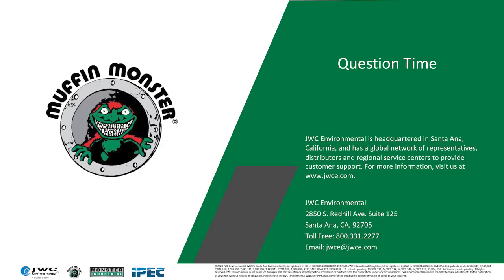Sure. Today we have a few clients that are using internally fed rotating drum screens for digester clean out. They fluidize the digester and drain it down as much as they can. And as they're draining it, they're pumping that digester fluid through the drum screen to clean it while they're cleaning the digester. Obviously, that screened effluent coming out of the digester, they send to the headworks because it's got to go somewhere. It's already been screened out, and then they continue their process, removing solids until the digester is fully cleaned out.